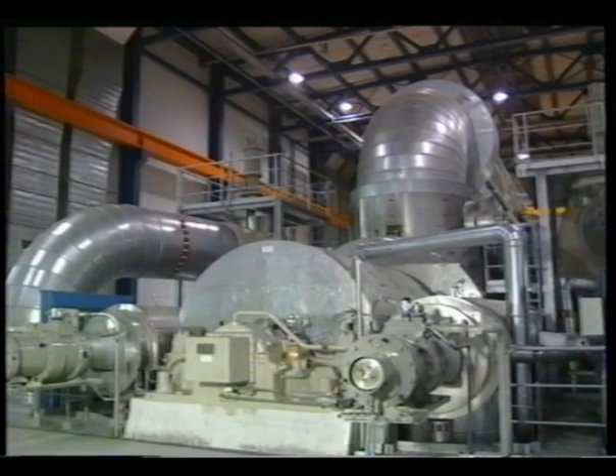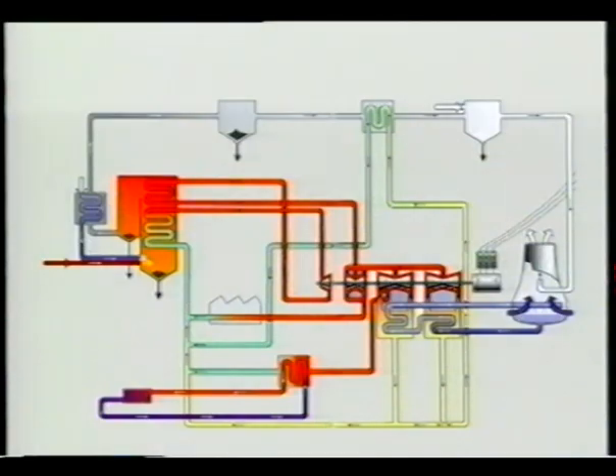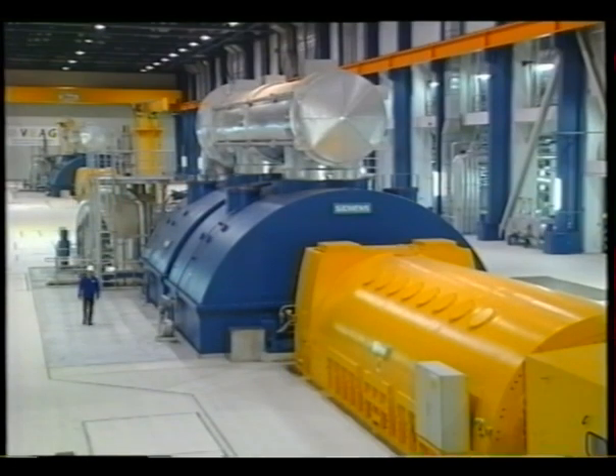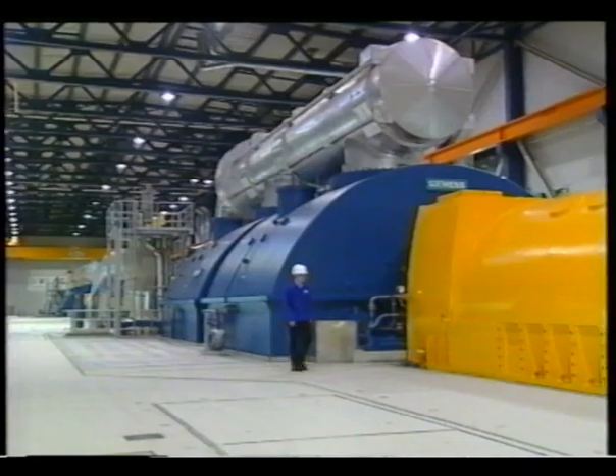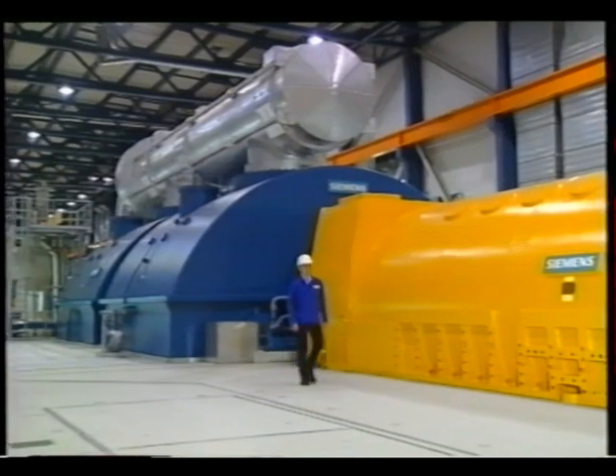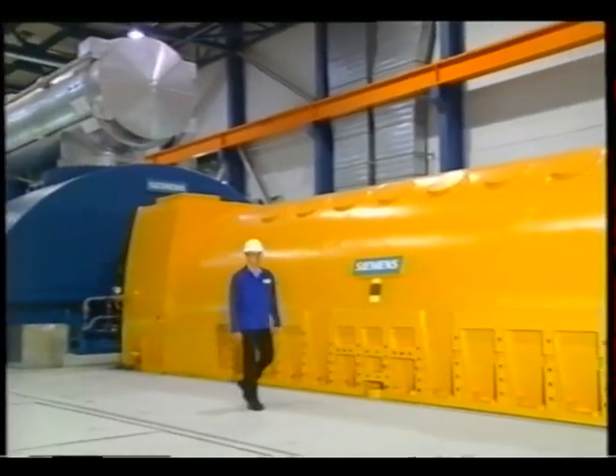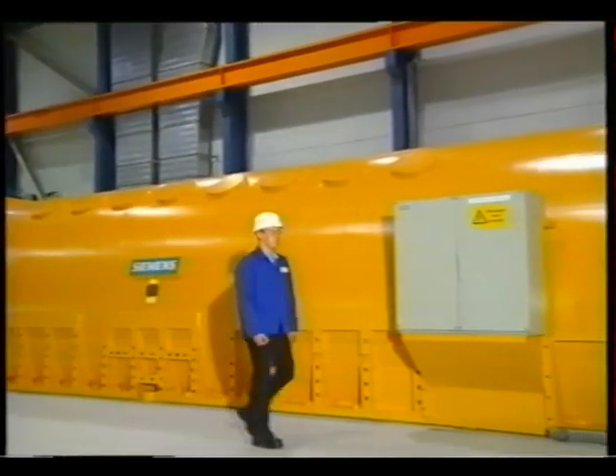The superheated steam first flows through the high pressure stage of the turbine. To reheat the steam, the intermediate pressure, it is channeled through the steam boiler and then back into the medium pressure stage of the turbine. Then it follows its way through the two low pressure stages. By flowing through the turbine, the thermal energy of the steam converts into movement. The turbine is linked to the generator by an axle.